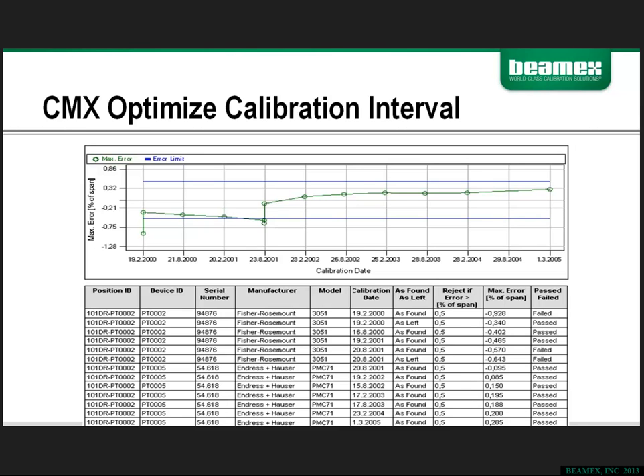And then if we look a little further down, you see that it passed the next 3 intervals, although if you look at it, the trend is getting worse with each successive calibration. So when it was initially adjusted and left, it was 0.340. The next interval, which was 6 months later, it drifted a little bit more, 0.402. The next interval, which was 6 months after that, it was at 0.465. And then subsequently went out of tolerance again 6 months later at 0.570. So at this point, the end user decided that it was time to replace this instrument. And as you can see here, they replaced that instrument in the same position with an Endress+Hauser PMC 71.